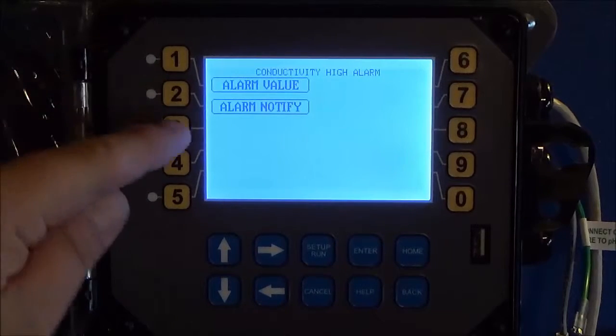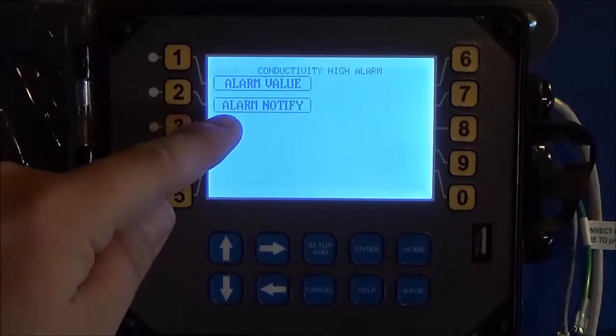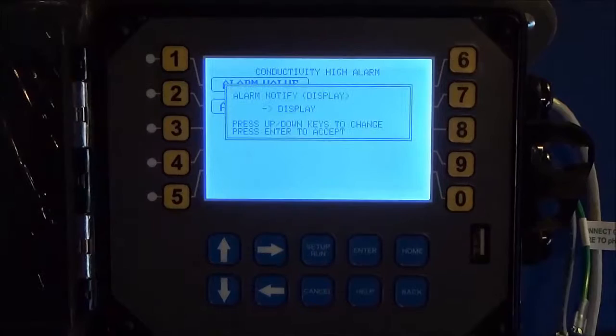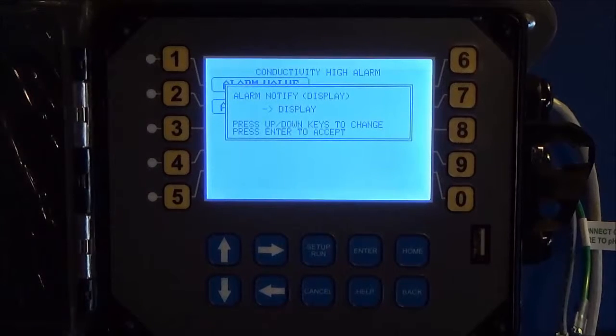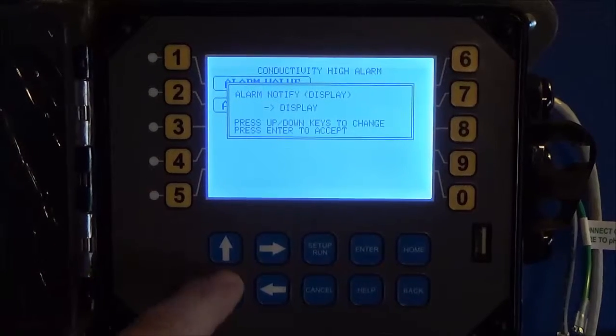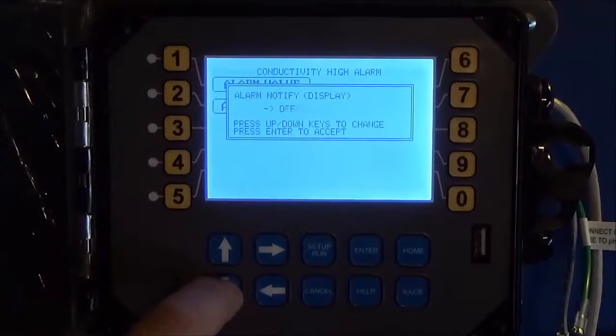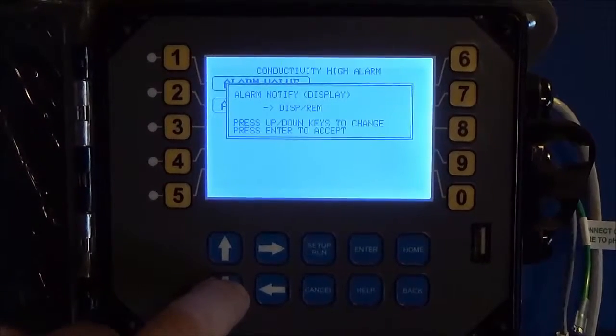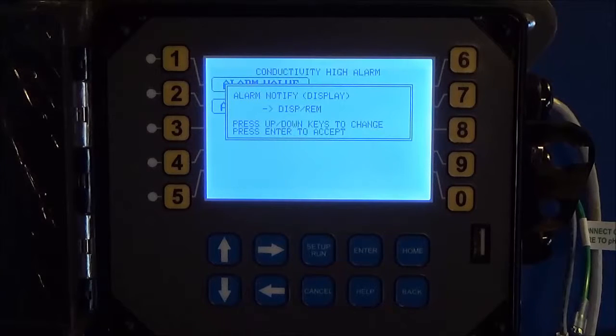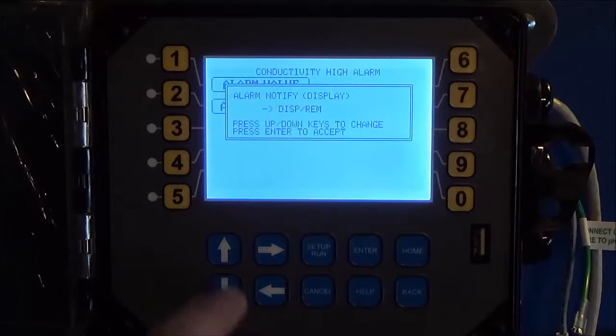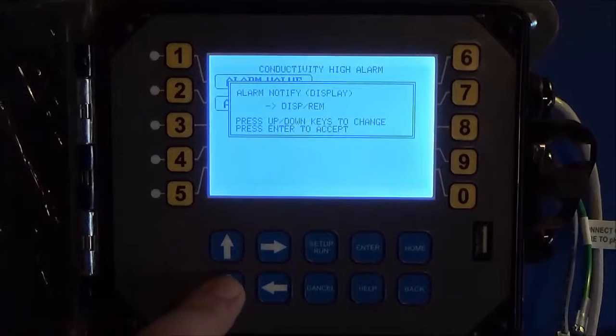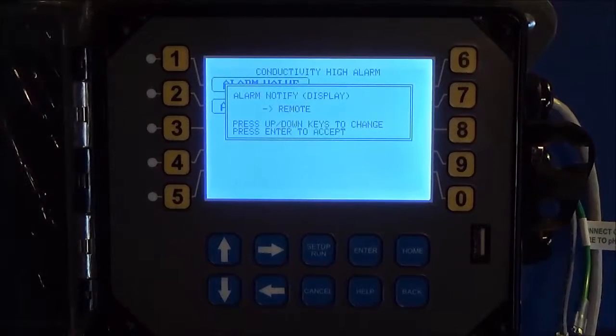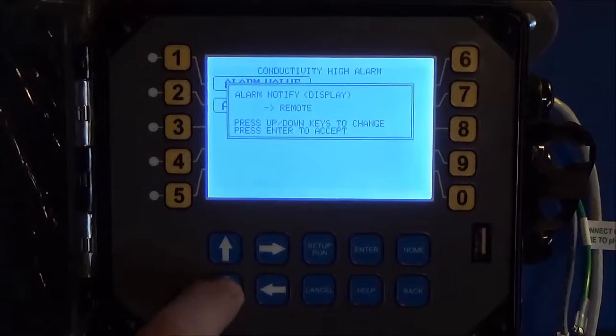Same thing except now the alarm value, there's also an alarm notify. And this is helpful if you have the unit connected to WebAdvantage. You can display only, so it only shows up here. You can turn it off completely. You can do a display remote, which means it'll show on the screen and also send an email alarm out if you have it set to do so. Or you can remote only, so it doesn't even show on the screen but it does send an email alarm.